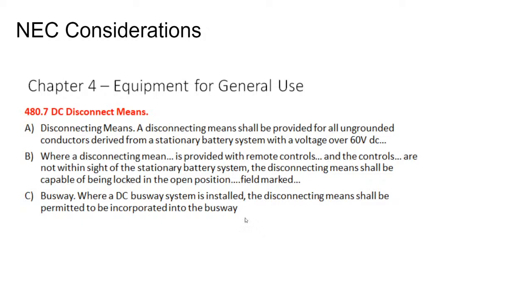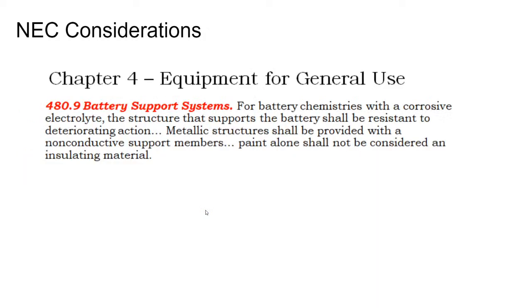There are disconnect requirements for the batteries. At the very least, there should be a disconnect within sight of the battery. So even if you have your battery system set up on digital load control so you can press a button and turn off all the parts, you still need a visible disconnect. And if you have an intelligent system with fewer disconnects, you still need a disconnect near the battery that can lock it in a de-energized position. Batteries can conduct electricity themselves, so they should be on an insulated pad or an insulated rack.